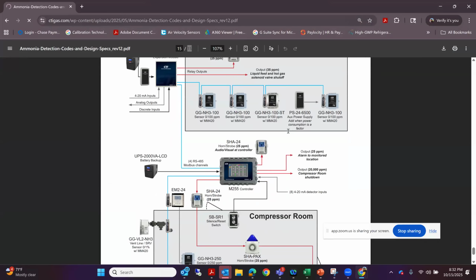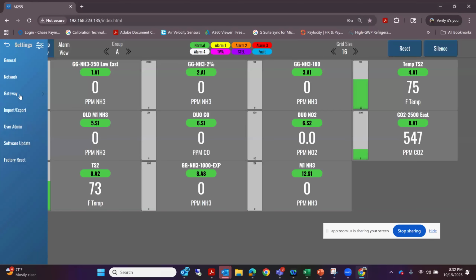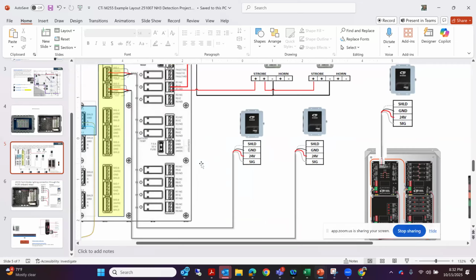With the Modbus web-based systems, the monitoring side's already covered, right? The PLC guys also want to be able to take this data. So if you decide to go with the standalone system that you can back up on your dedicated branch circuit and keep everything powered up and running for a while, you can feed this data straight back on the register. Any sensor on the system, concentration-wise, can be fed back through the internet as long as you connect the system to the internet, which is a fairly easy thing to do. This is the actual inside of the system.